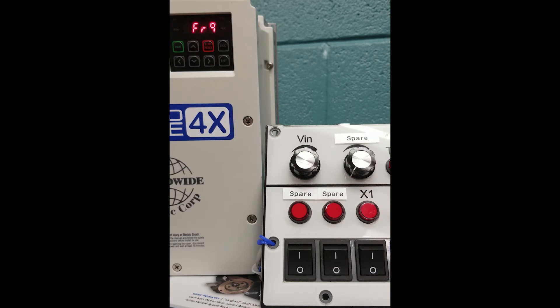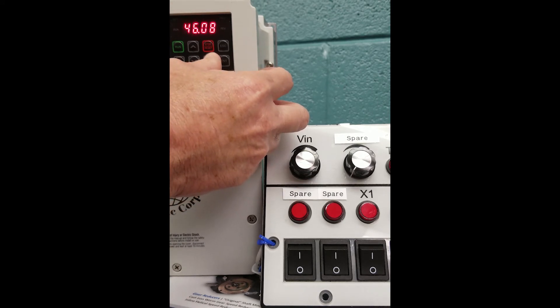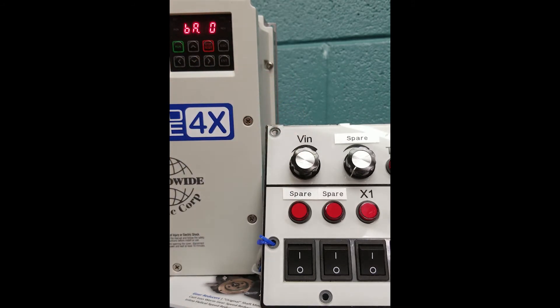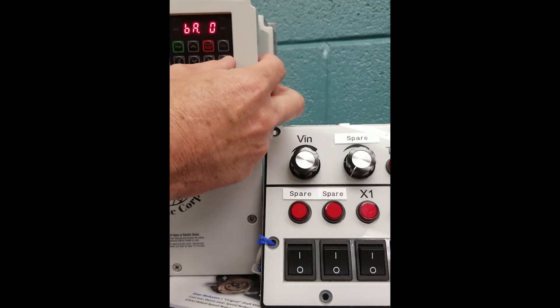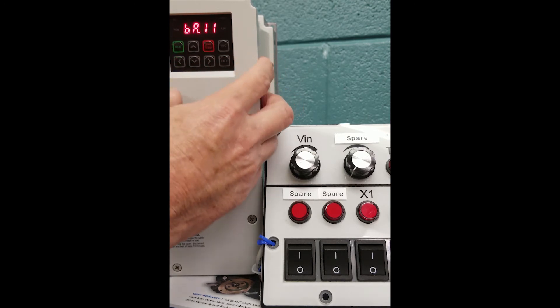Now we must go set our motor information into the VFD. We will do this by simply pushing the right arrow until we get to our BA parameters. We got BA. Please look at your instruction manual. We're going to go to BA 11, and this is going to bring us up to our motor poles.